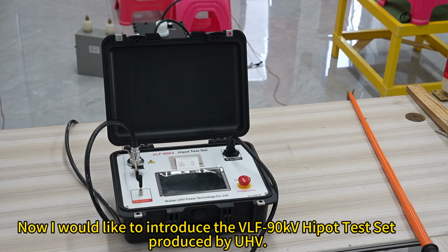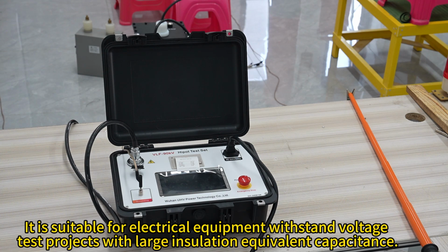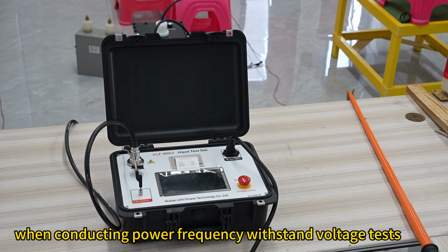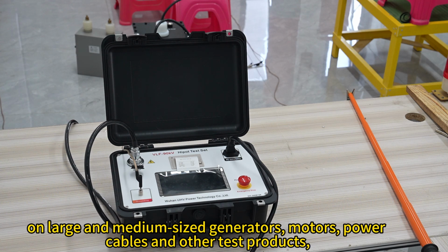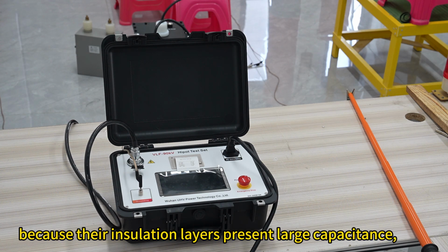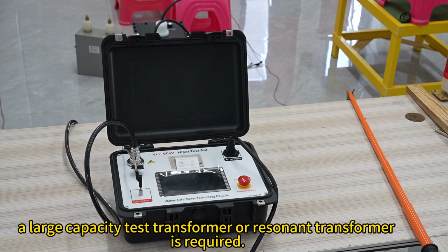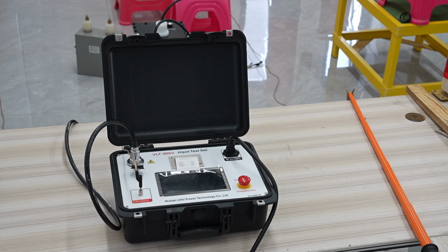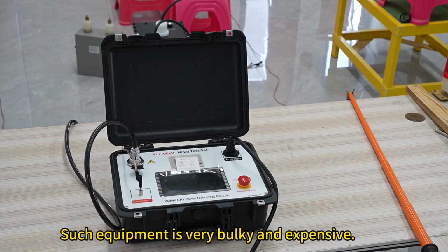Now I would like to introduce the VLF-90KV Hipot test set produced by UHV. It is suitable for electrical equipment with withstand voltage test projects with large insulation equivalent capacitance. When conducting power frequency withstand voltage tests on large and medium-sized generators, motors, power cables and other test products, because their insulation layers present large capacitance, a large capacity test transformer or resonant transformer is required. Such equipment is very bulky and expensive.